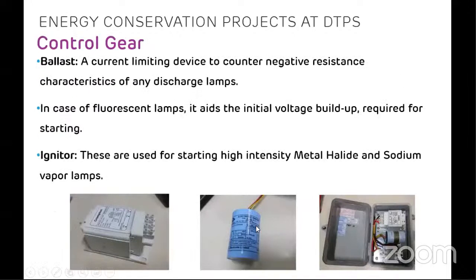There is also control gear installed with a lighting. There is a ballast and igniter. Ballast is a current limiting device. In the case of discharge lamps like tube lights or sodium vapor lamps, they draw very high current during starting. A discharge lamp has a negative resistance characteristic. Therefore, it draws very high current in starting. So the ballast will limit the current and voltage buildup, and it will provide only sufficient energy for the lamp to start. An igniter is commonly known as a starter, and the ballast is commonly known as the choke. The starter is required for high intensity metal halide and sodium vapor lamps. It is basically a capacitor.